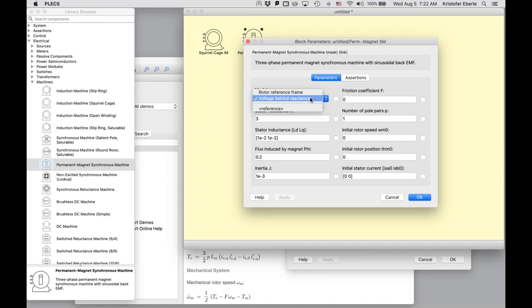So this is the voltage behind reactance or VBR implementation. It allows you to investigate the effects of dead time as well as failure modes and to develop mitigation strategies for those. So for the PM drive one potentially dangerous condition is tripping during flux weakening operation. That can result in uncontrolled currents and torques which is very undesirable. And unlike the traditional rotor reference frame model, the VBR formulations also allow you to directly interface to an arbitrary external network. So that could be a diode rectifier or open-circuited machine terminals.